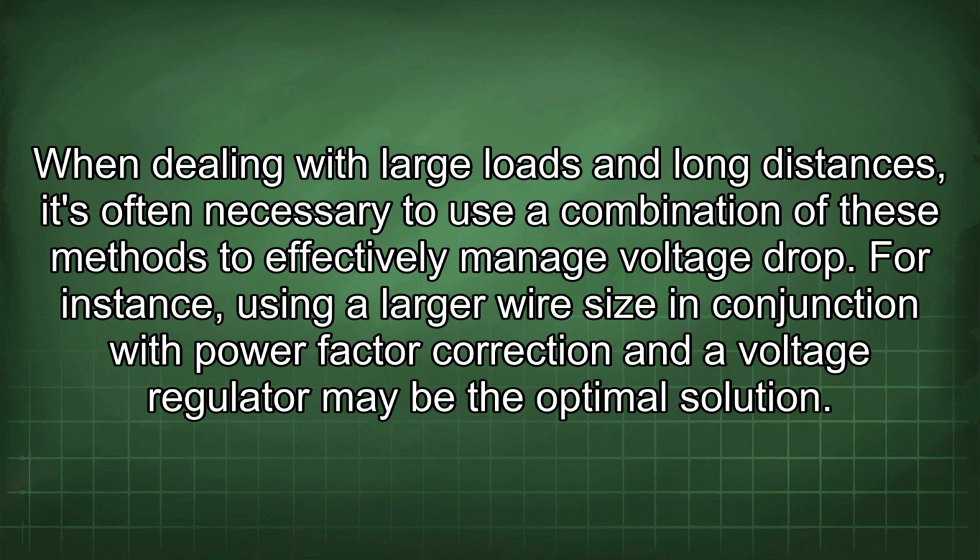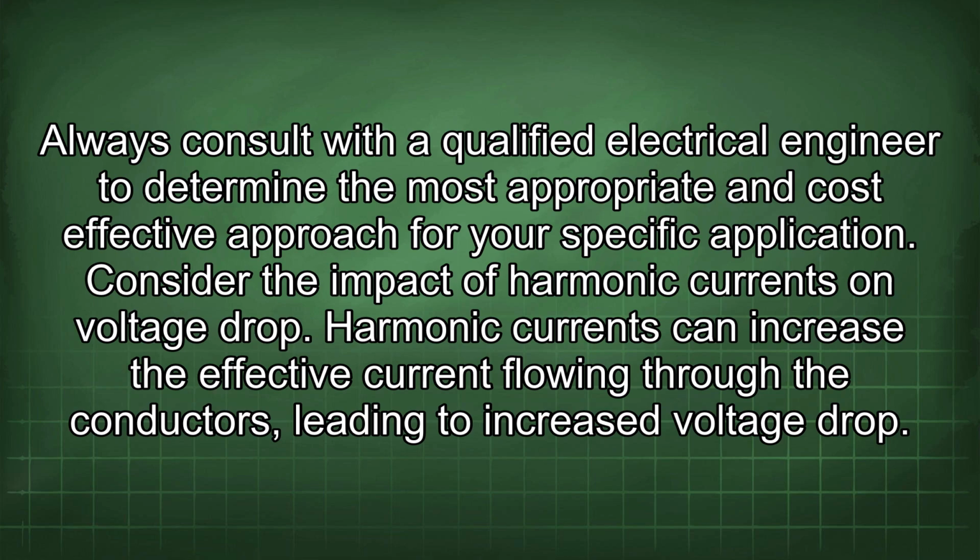When dealing with large loads and long distances, it's often necessary to use a combination of these methods to effectively manage voltage drop. For instance, using a larger wire size in conjunction with power factor correction and a voltage regulator may be the optimal solution. Always consult with a qualified electrical engineer to determine the most appropriate and cost-effective approach for your specific application.